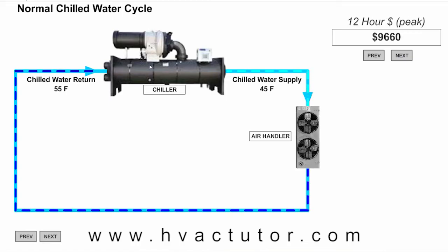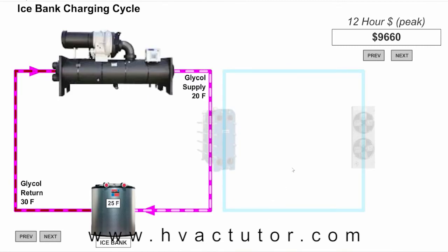During the peak hours, if we run this chiller nonstop, it can cost us roughly $10,000. So if we run it 12 hours off peak, it's costing us $348 as opposed to roughly $10,000. Most facilities are running their systems during the peak hours. The facility that we looked at used something called an ice bank. An ice bank is also called a thermal storage unit.